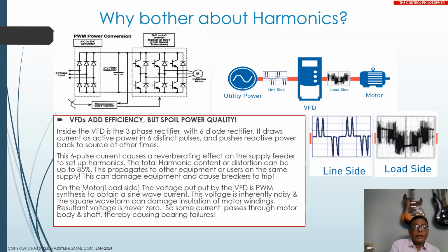It will cause some kind of eddy currents, and the high frequency harmonics can even travel through the bearings of the motor. The resultant voltage is never zero, so some current always passes through the motor body and shaft. It is not readily apparent. It is bad in some cases where people don't use filters. But ordinarily, if you take reasonable care, this is not such a problem.